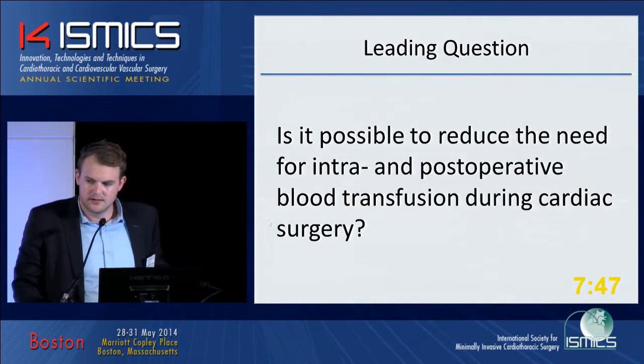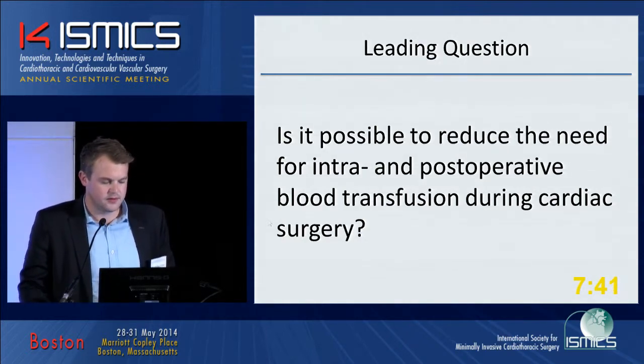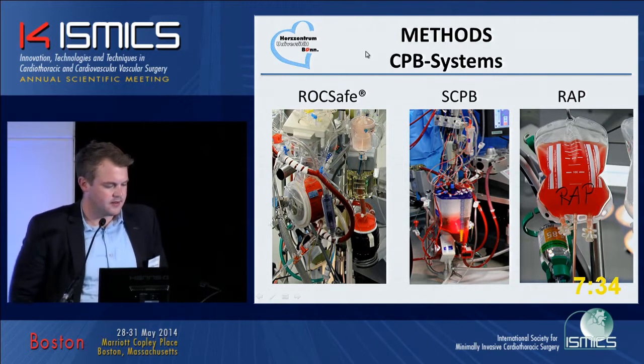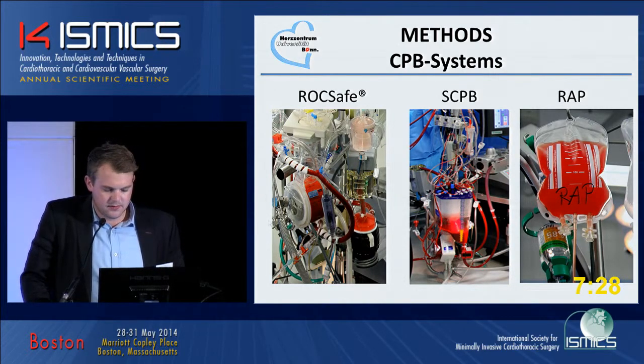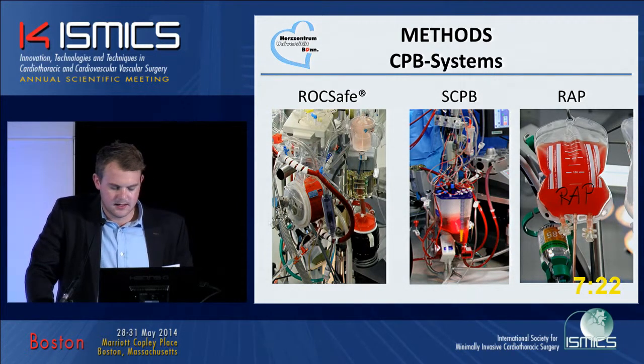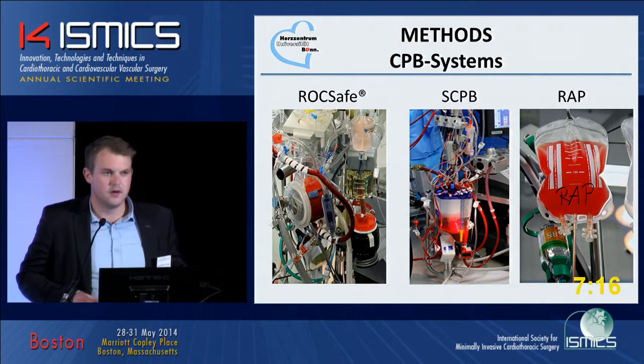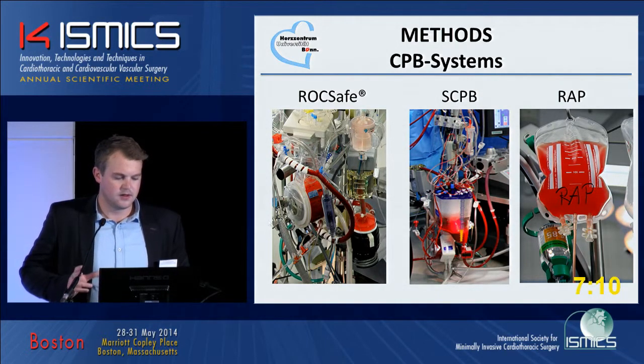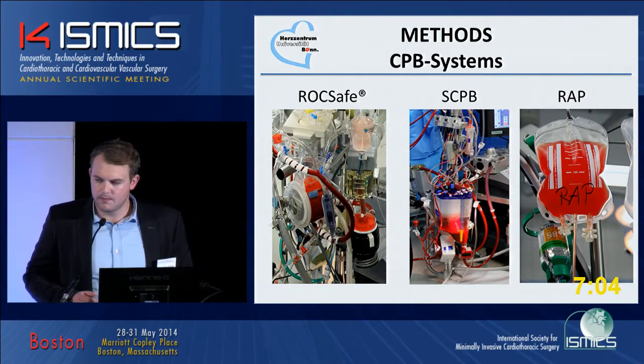Our leading question during the study was: is it possible to reduce the need for intra- and postoperative blood transfusion during cardiac surgery? We matched three ECC systems. On one side, the ROCSafe system as a mini-bypass system. There is a difference to the other two systems: there's a centrifugal pump instead of a roller pump, and there is no venous reservoir. That means there is no blood-air contact, and the foreign surface is also lesser than in the other groups.